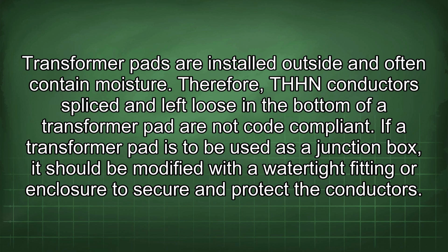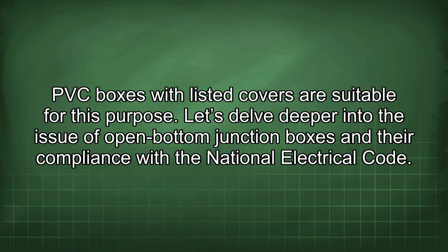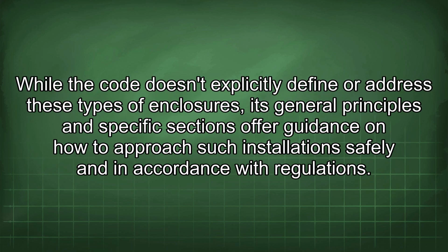If a transformer pad is to be used as a junction box, it should be modified with a watertight fitting or enclosure to secure and protect the conductors. PVC boxes with listed covers are suitable for this purpose. Let's delve deeper into the issue of open bottom junction boxes and their compliance with the National Electrical Code. While the code doesn't explicitly define or address these types of enclosures, its general principles and specific sections offer guidance on how to approach such installations safely and in accordance with regulations.